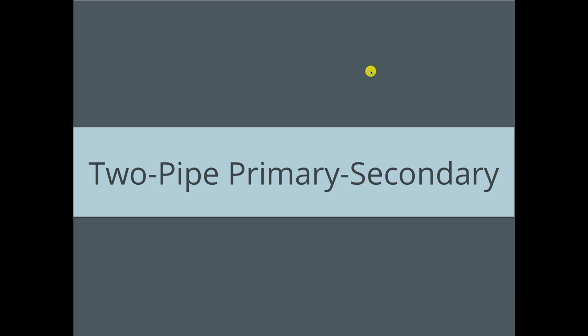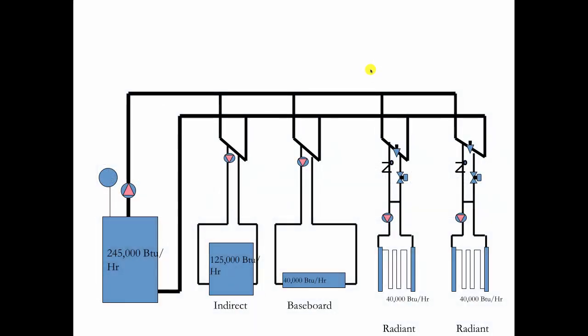Alright, two-pipe system on primary-secondary. Here's one way to do it. Now, the big advantage of primary-secondary is everybody's going to get the same temperature water. So as we leave at 180 degrees on this crossover bridge going into the return, it's 180-degree water, as it is here and here and here.